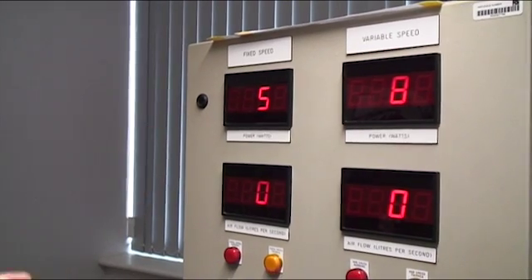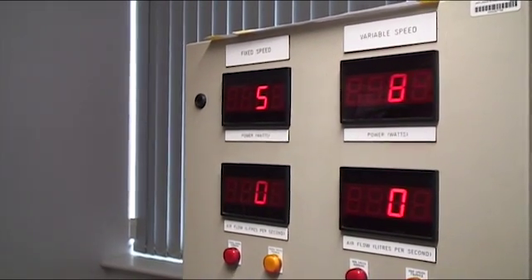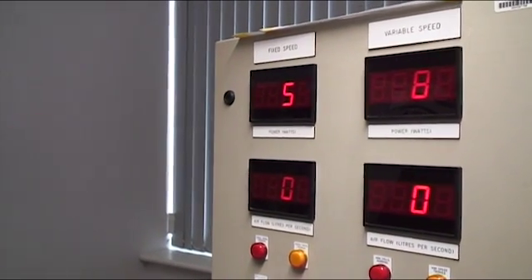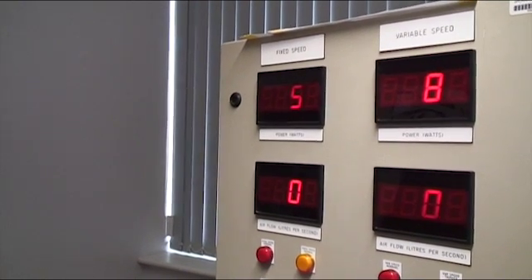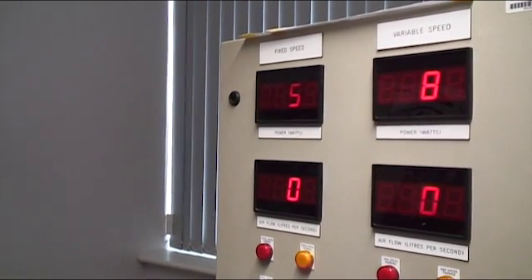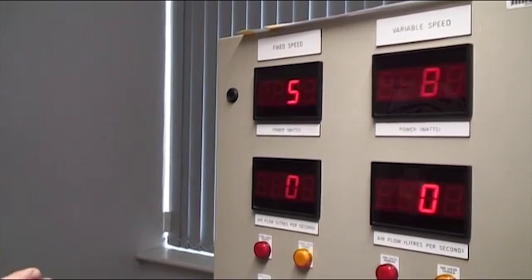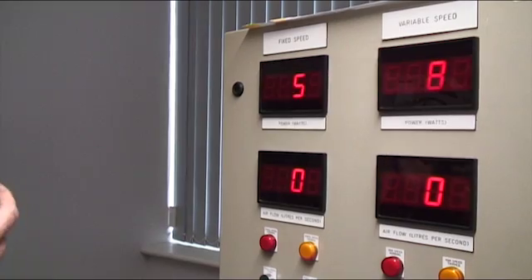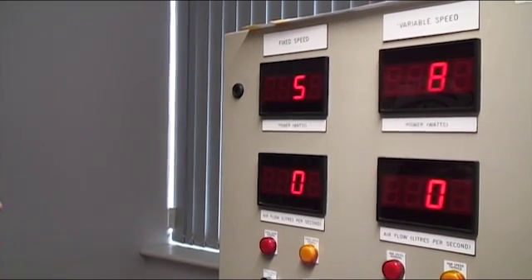Basically, we have a demonstration rig for inverters here. We actually have two fan systems. The one on the left is controlled by a damper, i.e. that's a paddle within the ductwork that will open or close the ductwork. And you have a fan running at constant speed that's pushing air against that paddle. So the paddle's acting as a throttle to restrict the airflow.